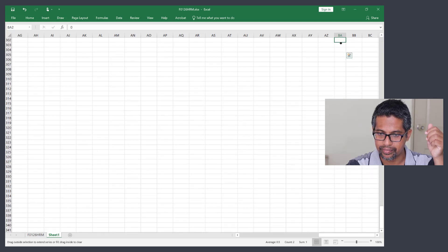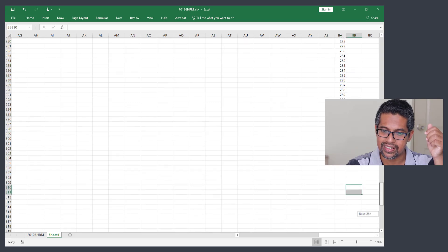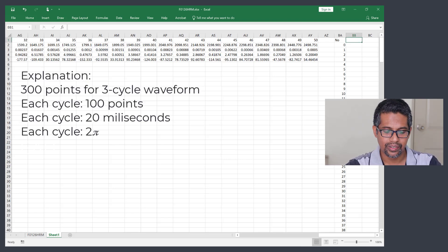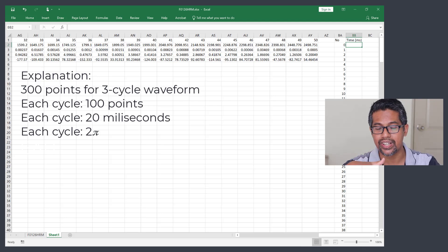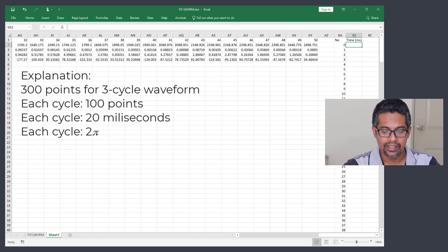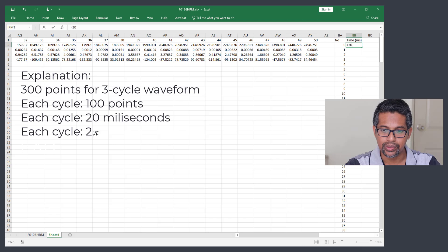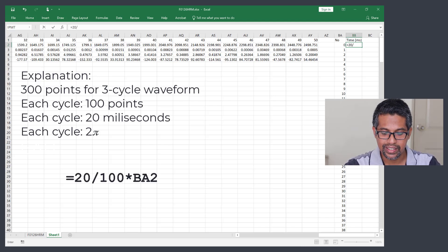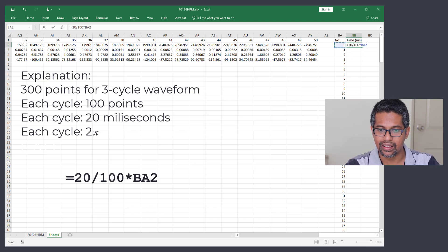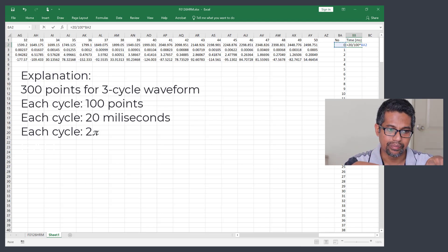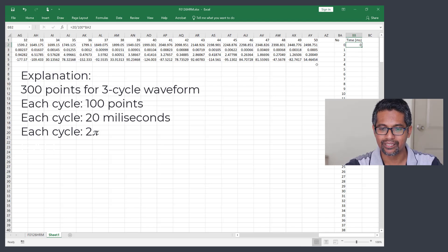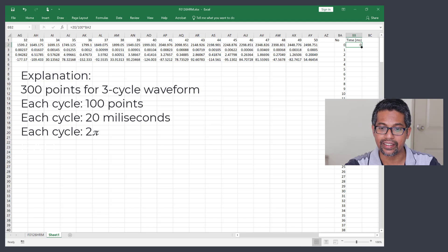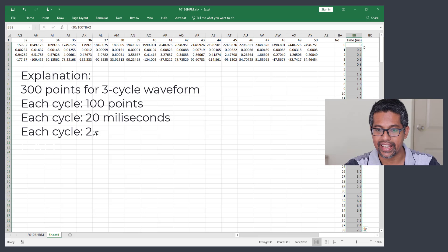We now have 300 cells filled. The next step is to put the time column in milliseconds. For this waveform recorded in Malaysia on a 50 Hz power system, one period is 20 milliseconds. Enter the formula: equals 20 divided by 100, times the cell on the left. Press Enter, then double-click the fill handle to fill down to the end of the row.